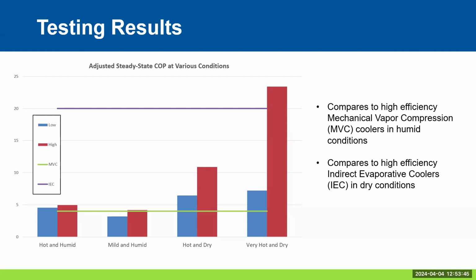Okay. And I'm trying to remember what our outside air fraction was that we used to calculate the mixed air condition the chamber ran at. Yeah, there were like 3: there was a 100, a 50, and a 35, something like that. That's all part of this calculation here. Okay, so it's targeting different applications, more realistic, like different ventilation. Yeah, if you didn't have too many occupants in a space, you'd have a lower outside air fraction, maybe 30%-ish. And if you've got more, like maybe a classroom, you might be more towards 50%. Or if you want this machine to provide all of the outdoor air and run as a DOAS, then it would be 100% outdoor air. Got it. Cool.